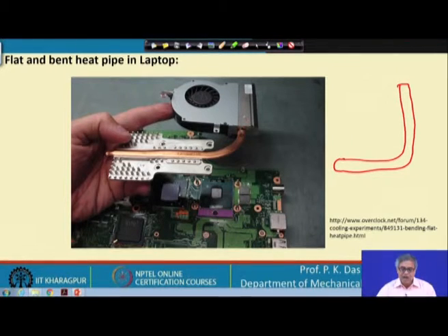In the condenser section, ultimately the heat has to be given off to the ambient. So, for efficient transfer of heat, on the condenser section we have fins, which I have mentioned earlier. Basically we have a number of fins over there. So, here heat is dissipated. How is heat dissipated? On this fin structure, if we circulate air at a high velocity, then heat will be dissipated.